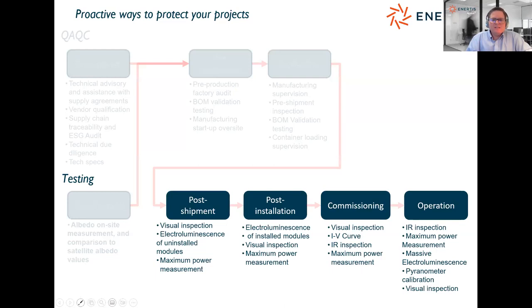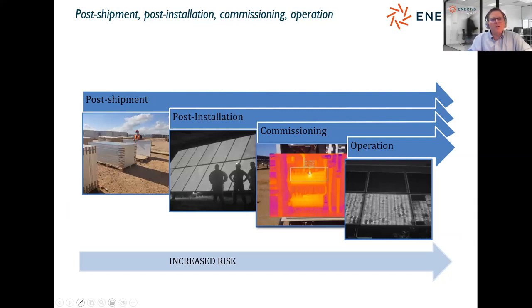The next phases kind of merge together in terms of procedures used, because pretty much all the procedures are applicable between these phases. But it's important to emphasize that the earlier they're used, the better, because you're lowering the risk. You lower the risk in two main ways. The first is you lower the financial impact of the risk by catching it early. Maybe you can correct it, or if you catch it early, you're not having to uninstall a lot of incorrectly installed materials. In addition, you can better assign responsibility. If you're detecting a problem that could have been caused in shipment or installation or operation, it's hard to assign that responsibility, and ultimately that is going to be a legal fight, or the owner is going to be forced to take responsibility.